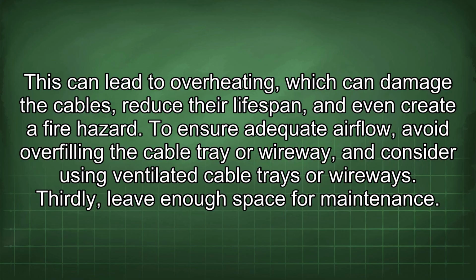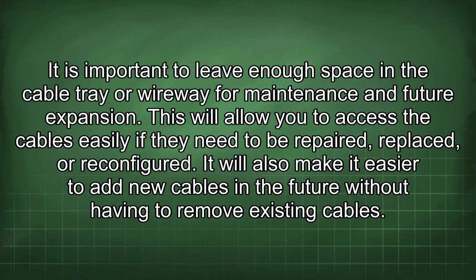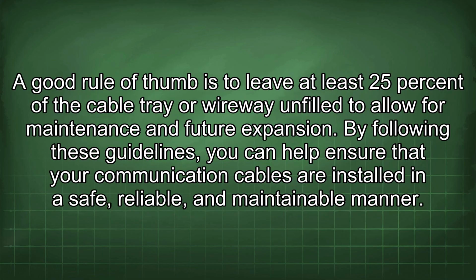Thirdly, leave enough space for maintenance. It is important to leave enough space in the cable tray or wireway for maintenance and future expansion. This will allow you to access the cables easily if they need to be repaired, replaced, or reconfigured. It will also make it easier to add new cables in the future without having to remove existing cables. A good rule of thumb is to leave at least 25% of the cable tray or wireway unfilled to allow for maintenance and future expansion.